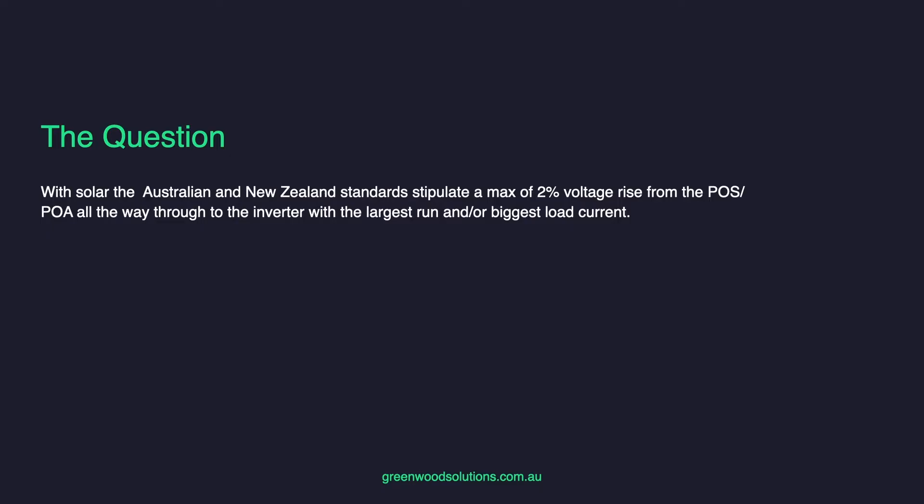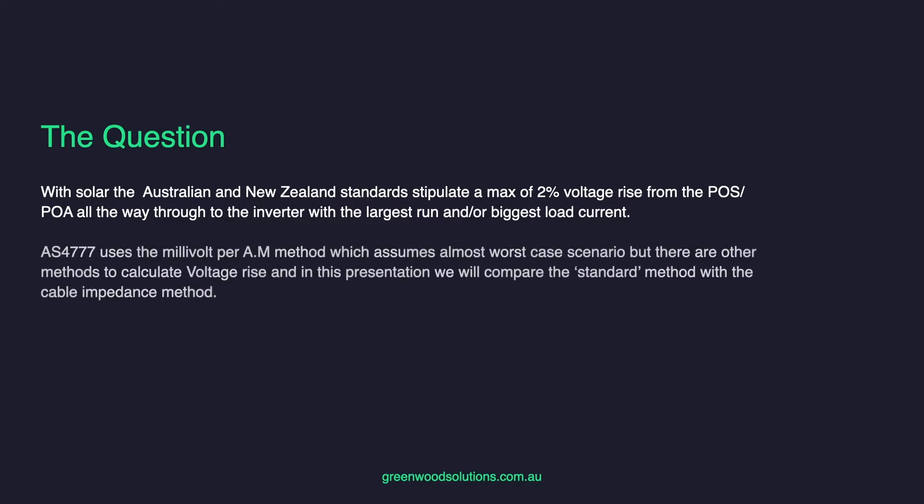The Australian and New Zealand standards stipulate a maximum of 2% volt rise from the point of supply all the way through to the inverter with the largest run and/or the biggest load current. AS4777 uses the millivolt per amp metre method, which assumes almost the worst case scenario, but there are other methods to calculate voltage rise. In this presentation, we will compare the standard method with the cable impedance method.